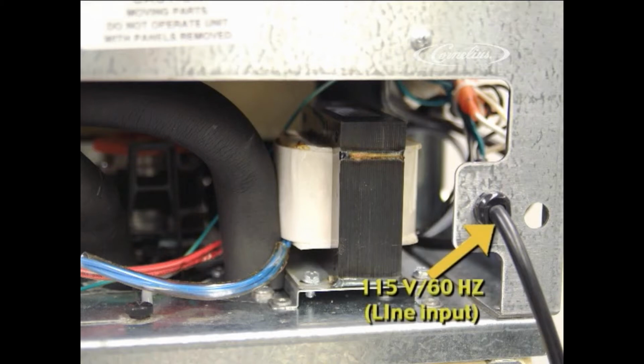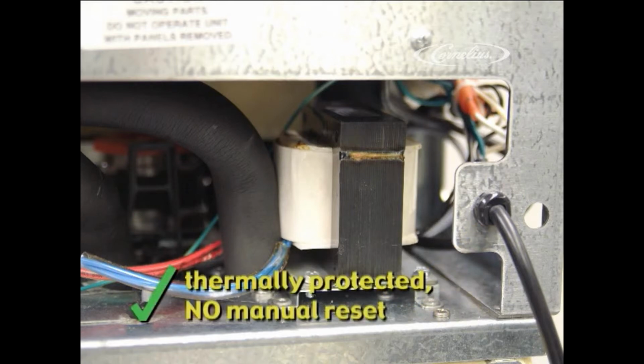This transformer is equipped with overload protection. Should it become overloaded and a buildup of heat occurs, the transformer will kick out on the overload. When cool, the overload resets. It does not have manual reset capability.